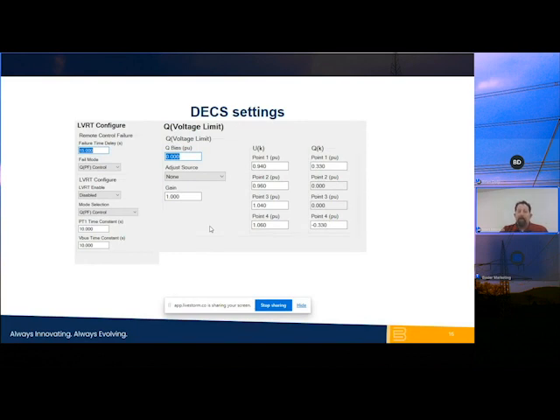All of those reactive power controls, we can set up within the DECS. These are just a few screenshots. There are multiple places within the product where these need to be set up, but it's very configurable. There are a lot of points in here. But again, you're setting a set point based upon how you want the synchronous machine to operate when connected to the grid, again, for stability.